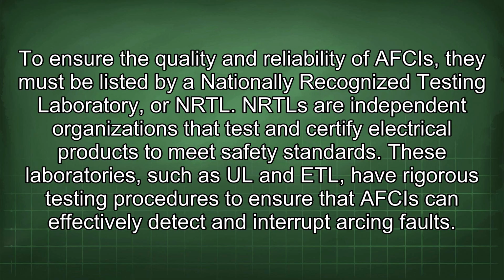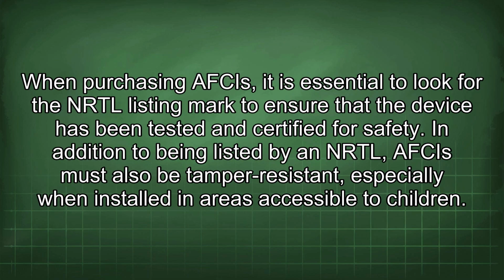To ensure the quality and reliability of AFCIs, they must be listed by a nationally recognized testing laboratory, or NRTL. NRTLs are independent organizations that test and certify electrical products to meet safety standards. These laboratories, such as UL and ETL, have rigorous testing procedures to ensure that AFCIs can effectively detect and interrupt arcing faults. When purchasing AFCIs, it is essential to look for the NRTL listing mark to ensure that the device has been tested and certified for safety.